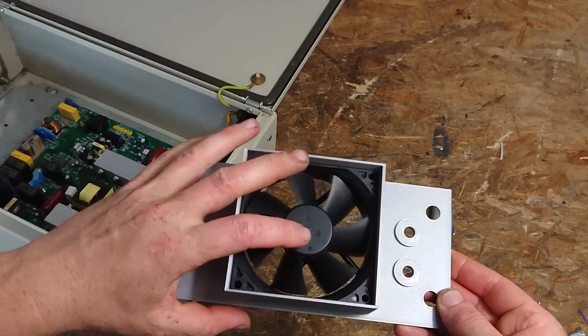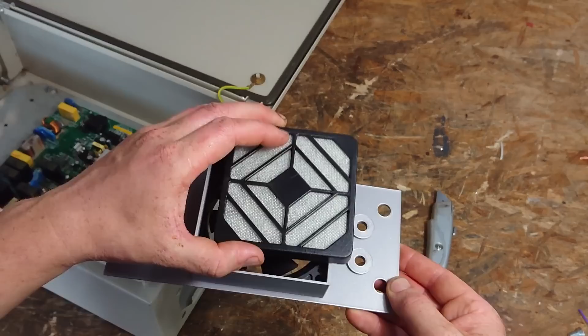This plastic part will not only close the enclosure but will also house a bigger fan than the tiny one that came with the UPS. A dust filter is installed as well, in order to prevent dust from clogging up the heat sinks and electronic components.